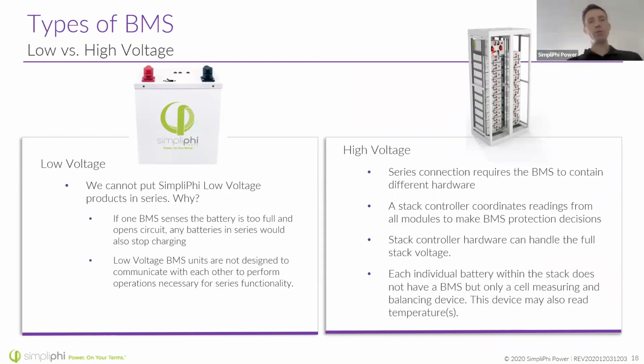We have both low voltage and high voltage BMS units. So why can we not stack our low voltage batteries in series? You cannot take two 24-volt SimpliPhi batteries and put them in series to make a 48-volt battery, or three to make a 72-volt battery. We never do that, because any individual battery in a series chain can disrupt the others from performing. Balance is key.